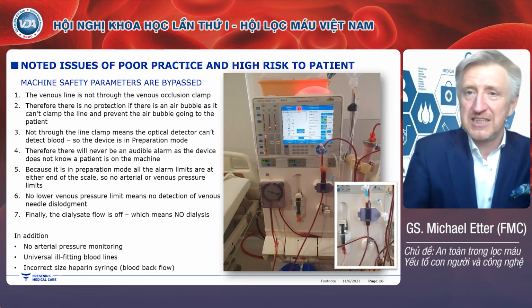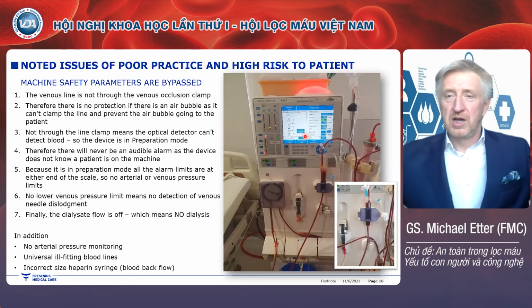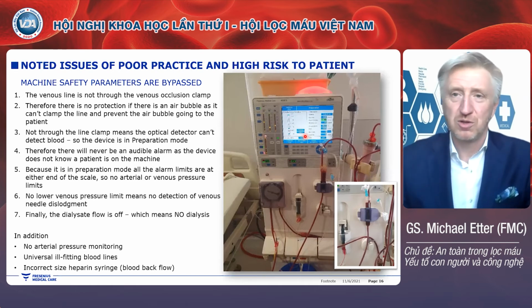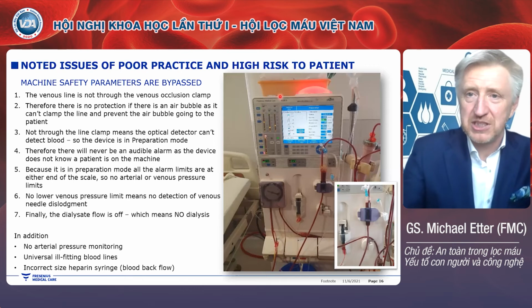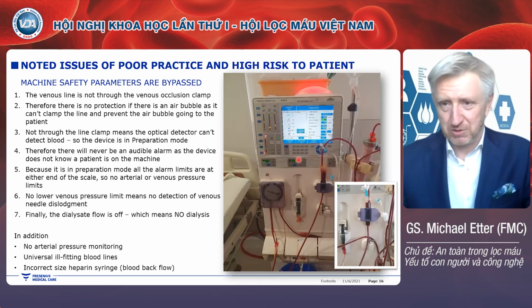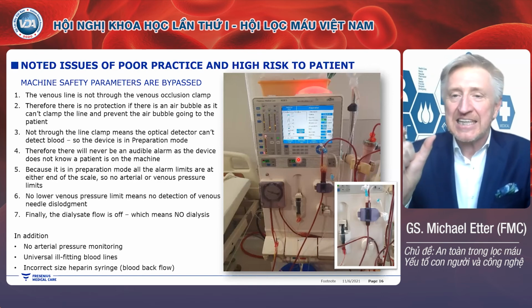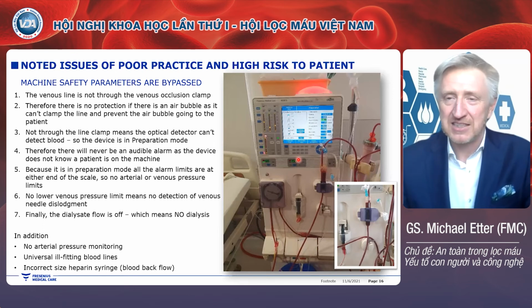In this machine, you see here, it is still in preparation mode. When you're in preparation mode, all your alarms are deactivated. Look at this here. All the alarm triggers are on the upper and lower ends. That means they are not set, they are not active. So this machine is flying blind, no control whatsoever. And the other problem is, of course, that if you do not activate the treatment and the machine runs in preparation mode, there's no dialysate flow. So there is no dialysis going on. You can see a little error on this setting can create a lot of problems.